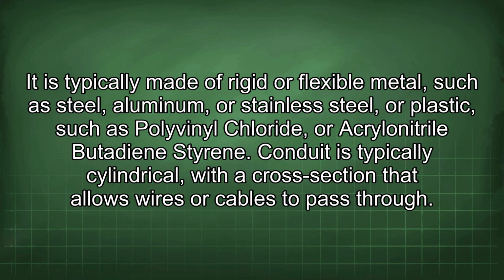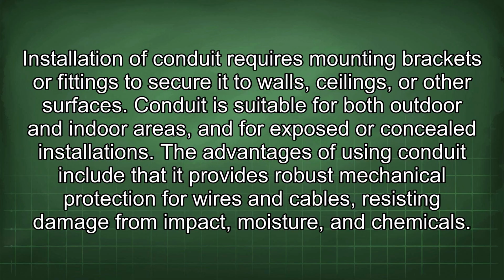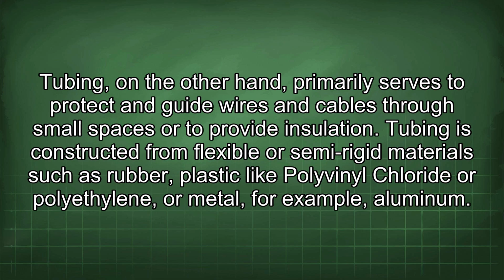Conduit is typically cylindrical with a cross-section that allows wires or cables to pass through. Installation of conduit requires mounting brackets or fittings to secure it to walls, ceilings, or other surfaces. Conduit is suitable for both outdoor and indoor areas, and for exposed or concealed installations. The advantages of using conduit include that it provides robust mechanical protection for wires and cables, resisting damage from impact, moisture, and chemicals.